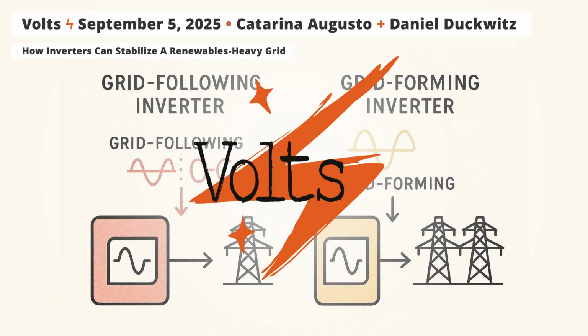That means if you switch on your stove or anything larger happens, the voltage will remain a stiff voltage source, and the current needed will just begin to flow according to the needs. That in turn impacts the frequency that the grid forming inverter makes, or the internal state of frequency in its control system. So that's the fundamental difference - it's not observing and following, it is making it. If it notices there is higher load, it will adjust its internal frequency. That's the fundamental difference between grid following and grid forming.